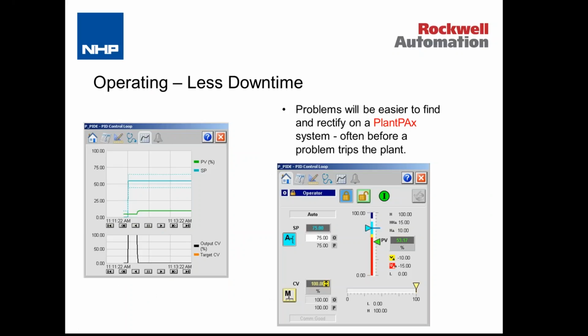And then once the system is up and running on the operation of the plant, potentially less downtime. Problems are typically easier to find and rectify in a Plant PAX system. The diagnostics that are available via the faceplates are typically far more extensive than what you would find on a non-Plant PAX system. Most people just don't have the engineering budget, the time to develop the level of diagnostics that are available in the Plant PAX library. The tens of thousands of hours that Rockwell have put into developing these over the last 10 to 15 years, most people just don't have that luxury of being able to do that.